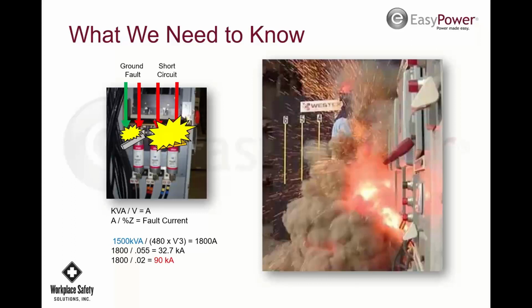So a fuse, it'll say a fuse is from a half a cycle to 2 cycles. And in reality, you can get even tenths of a cycle with some of these new electronic fuses. So it's very quick and very fast acting. Breakers may be 1.5 cycles for molded case breakers, and you could go all the way up to 30 cycles for time delay breakers for motor controls or VFDs and things like that. So where you have 30 cycles, that's like a total engulfment of your body into this arc flash. So you can get some really high arc flash levels. Hopefully that answered your question.